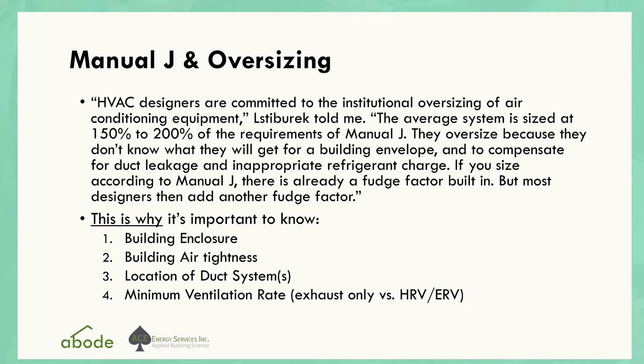Designers are committed to institutional oversizing of air conditioning equipment. This is in Green Building Advisor. The average system is sized at 150 to 200% of the requirements of the Manual J. They oversize because they don't know what they will get for a building envelope, and to compensate for duct leakage and inappropriate refrigerant charge. If you size according to the Manual J, there is already a fudge factor built in, but most designers add another fudge factor.